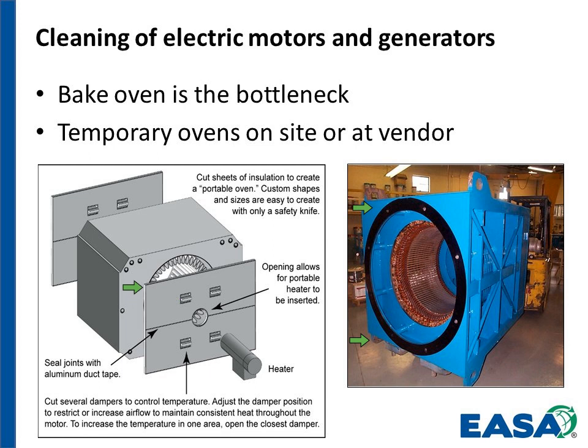There are home construction materials available at the large box stores that we all go to for home projects. The hard foam board with aluminum on both sides can be very easily duct taped onto a stator. The one on the right is shown in the image here, and we can use supplemental heating. That may be space heaters, it may be the salamander or torpedo blower that you see on the right, in order to push hot air through this and dry the windings effectively and efficiently without tying up the shop's single bake oven for 10 or 12 hours to dry it.